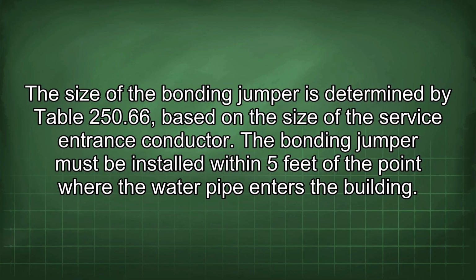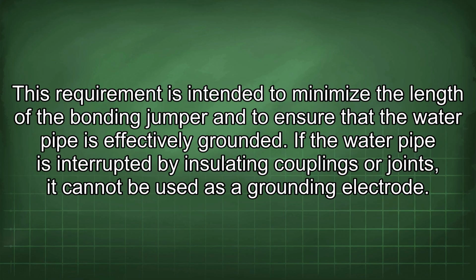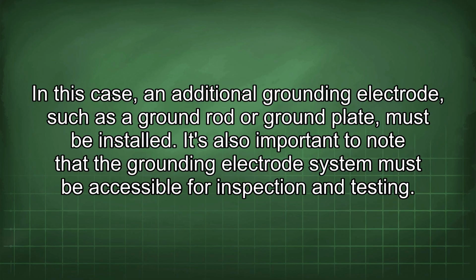The bonding jumper must be installed within 5 feet of the point where the water pipe enters the building. This requirement is intended to minimize the length of the bonding jumper and to ensure that the water pipe is effectively grounded. If the water pipe is interrupted by insulating couplings or joints, it cannot be used as a grounding electrode. In this case, an additional grounding electrode, such as a ground rod or ground plate, must be installed.